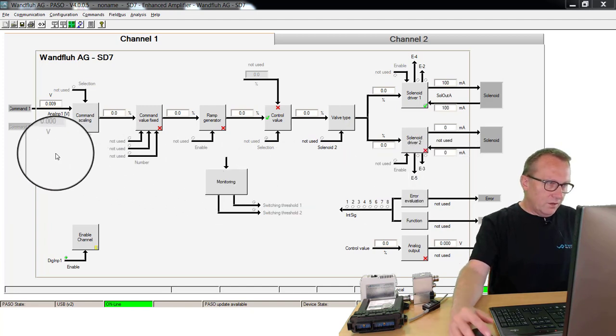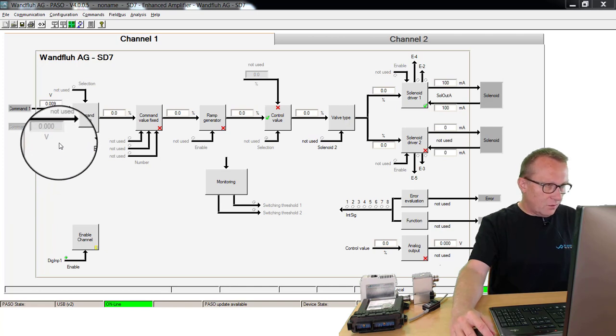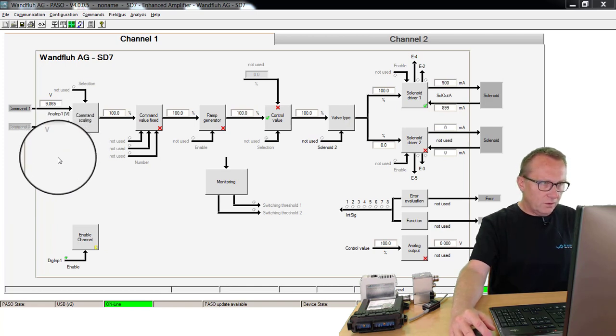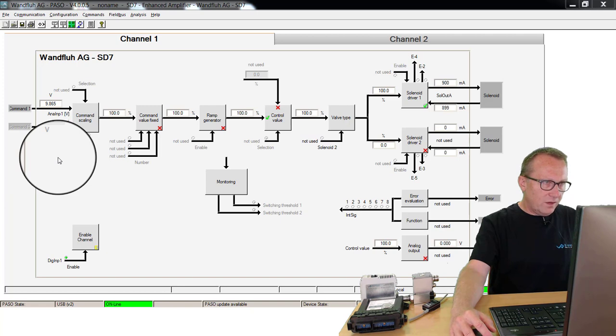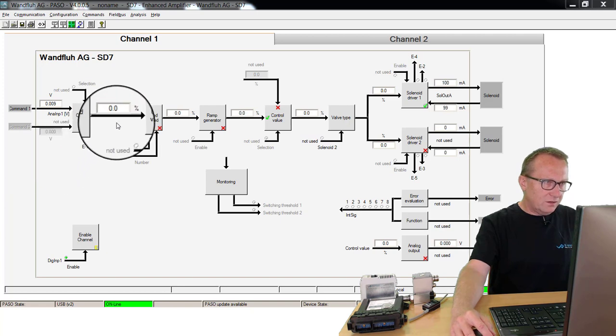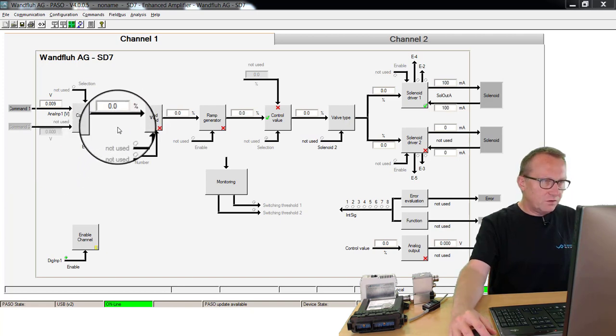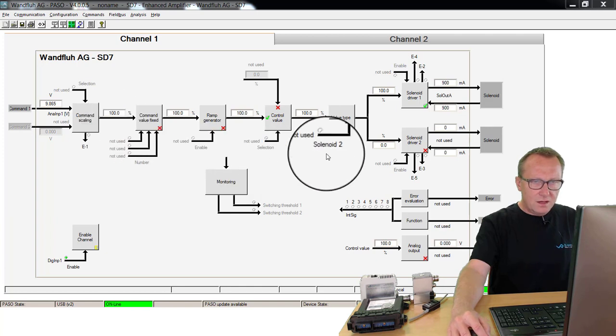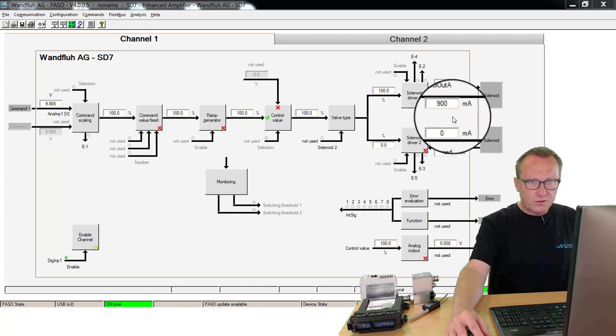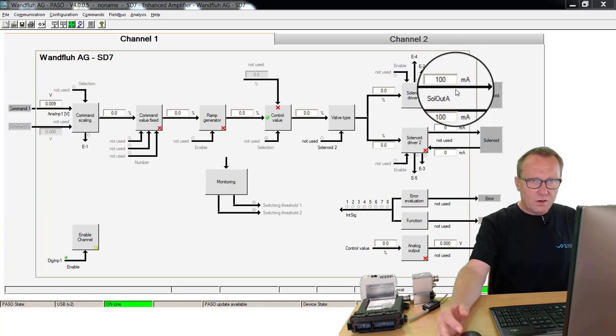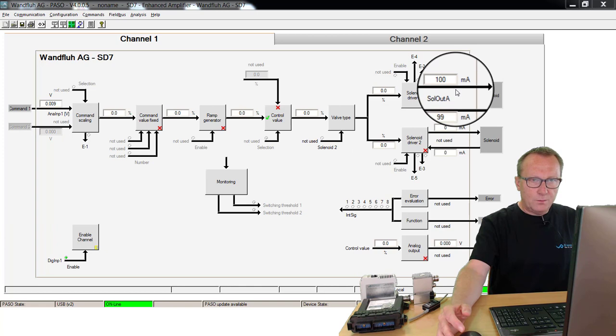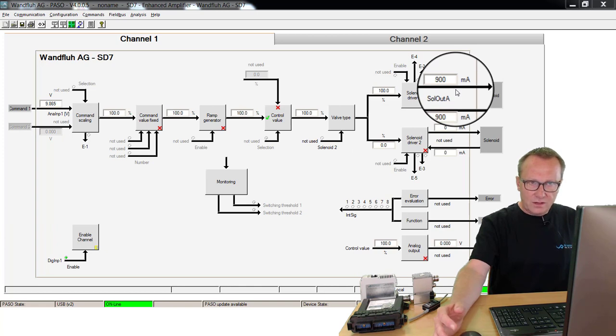In today's application, I have a command value from 0 to 10 volts. With this command value, I can generate the internal signal from 0% to 100%. On the output side, I will have 100 mA to 900 mA.